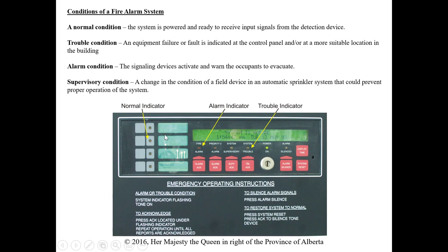The conditions a fire alarm system can be in: under normal condition it's powered and ready to receive input signals from field detection devices — smoke detectors, heat detectors, pull stations — waiting for a change in state. A trouble condition is not an alarm; it just indicates something isn't right with the system. It could be a broken wire, a loose wire, or a piece of field equipment not working properly — basically an open in the circuit.